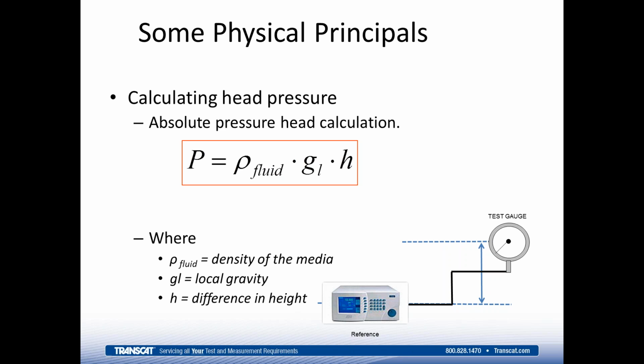at two different heights, even if they're opened up to the same test system, the same media, they will be seeing two different pressures. In the example here where we have the dial gauge off to the right that's higher, that's above our pressure controller, the test pressure or the pressure that the dial gauge is seeing will be slightly less than the pressure that the reference is seeing. This is caused by, as we said, this head height. Now, the density is a key aspect of this, and the density of the fluid will be different depending upon if it's a gas or a liquid.